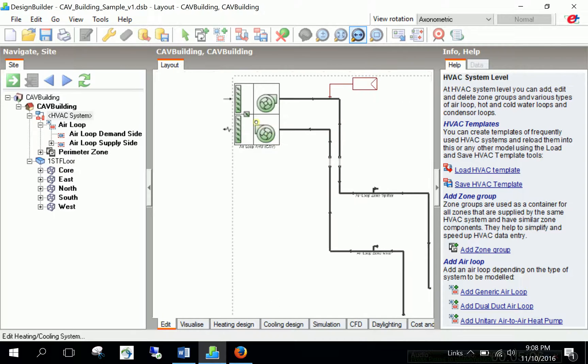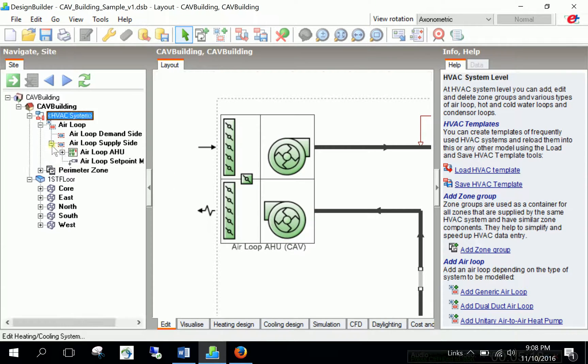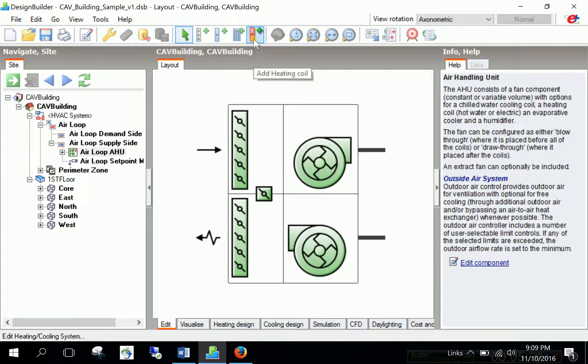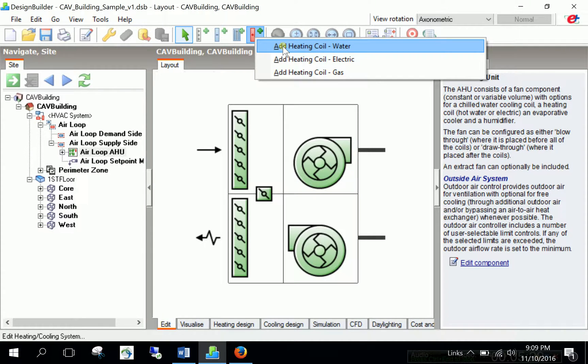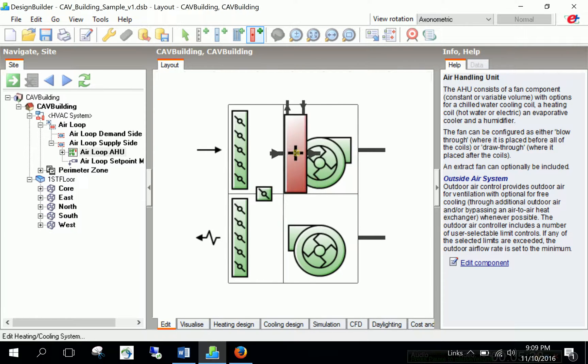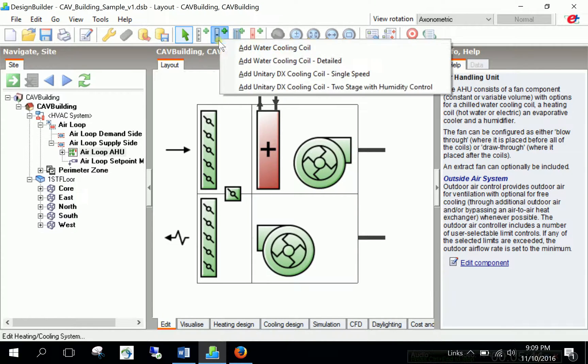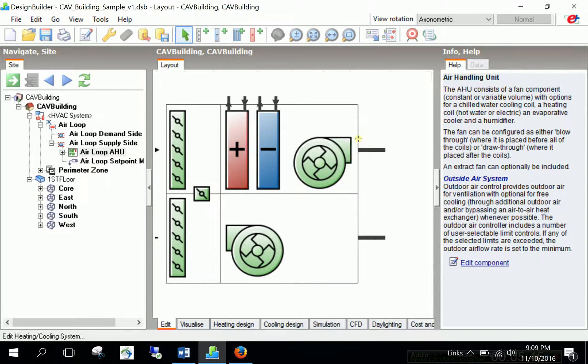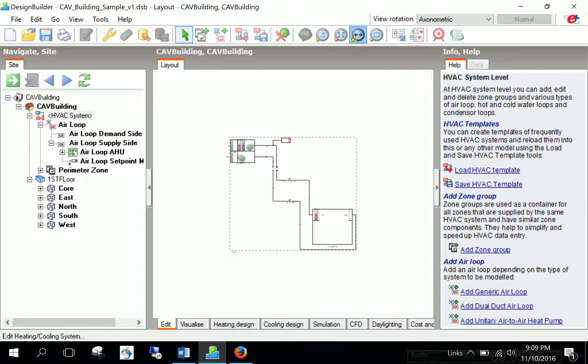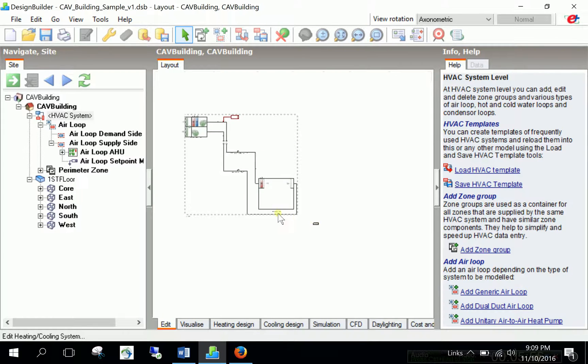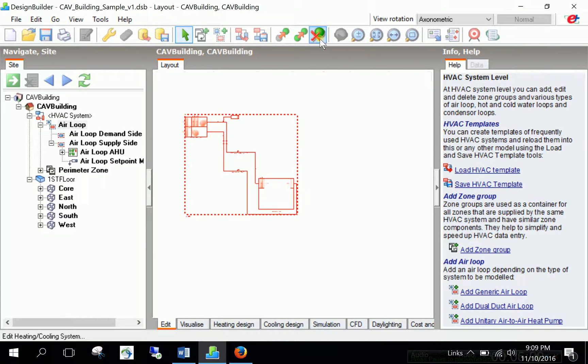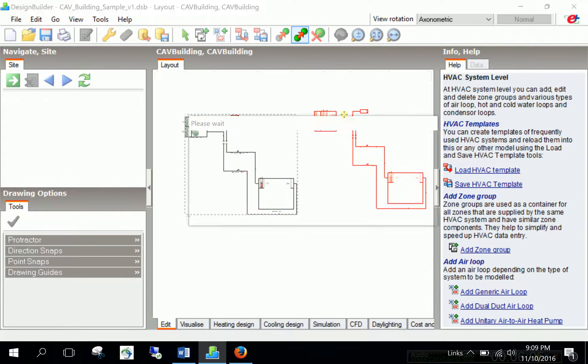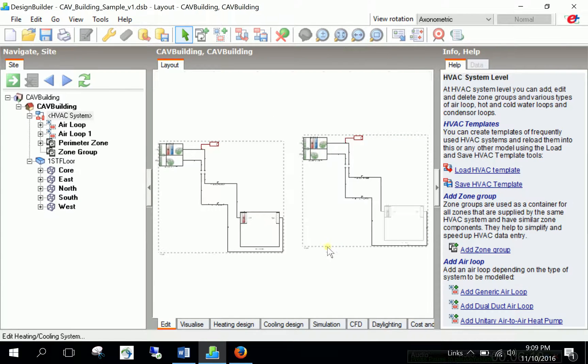Okay. This is easy. Just connections made. But we are missing some components again. We are missing the heating and cooling coil at the AHU. So, all I need to do is just go to the AHU. And then look at the tabs on the top row. And look at add heating coil. Click and add heating coil water. Not electric. Not gas. It's a hydronic system. So, we should add water. So, add it just before the supply fan. Click. Escape. I don't want it. Another one. And then this time go up and choose water cooling coil. And say okay. And edit. And now heating coil, cooling coil are added. So, now this is a system. But this is a CAV system. Is done. So, again similar to the previous one. You can select the entire thing. And just clone. Right. By copying and copy paste. Basically duplicating it. And you can do it as much as you want. As much as you need. Okay. Based on your building design.